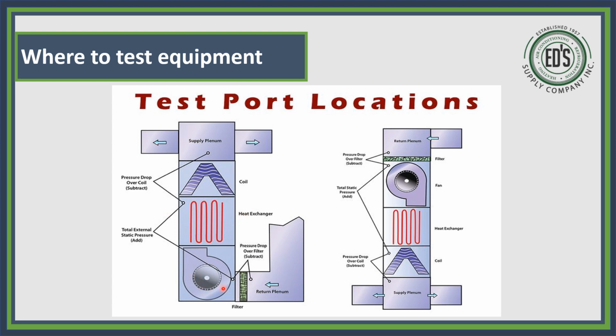Now, when you're checking your static pressure with the dual manometer that we showed you, you will have a couple of test ports. The furnace, which is this part here, this blower and this section here, is rated from the factory to have an external static pressure. Now, they don't take your coil into consideration because that's separate. It's considered an accessory. Anything separate from the actual furnace is considered an accessory. So the static pressure that you read on your panel is just for this space here. And then you have this deadhead to worry about. And you have these takeoffs to worry about. You have this filter to worry about. And you have this 90 degrees here to worry about. All these are going to cause issues with your static pressure, or issues, turbulence, let's say.